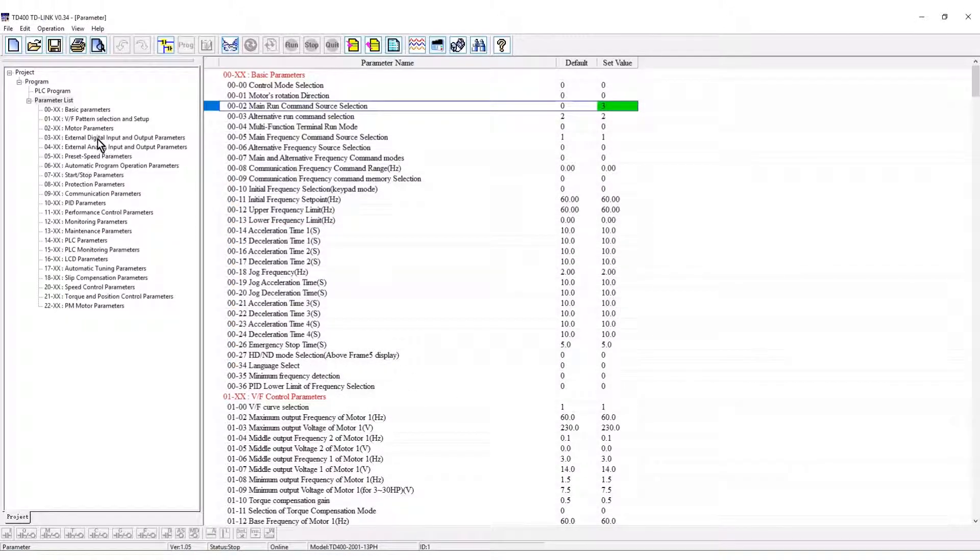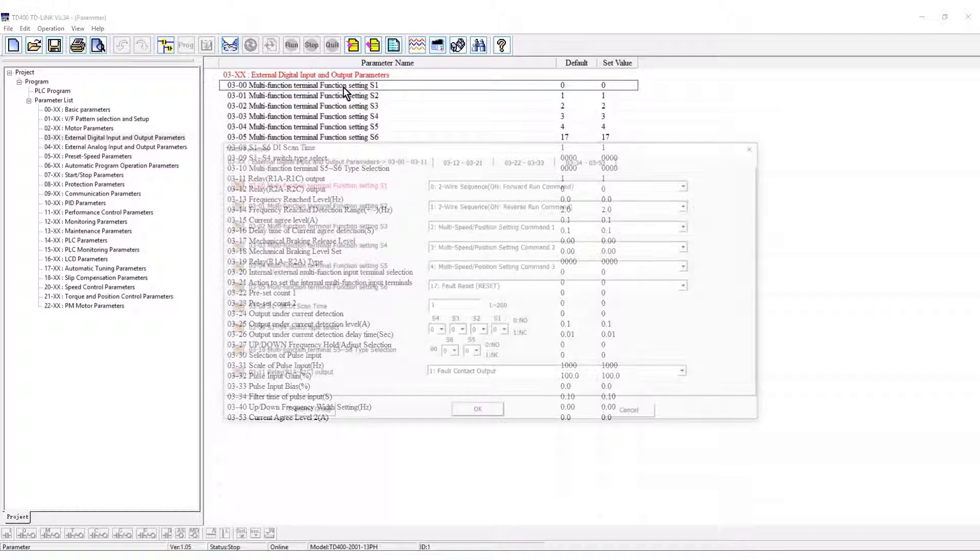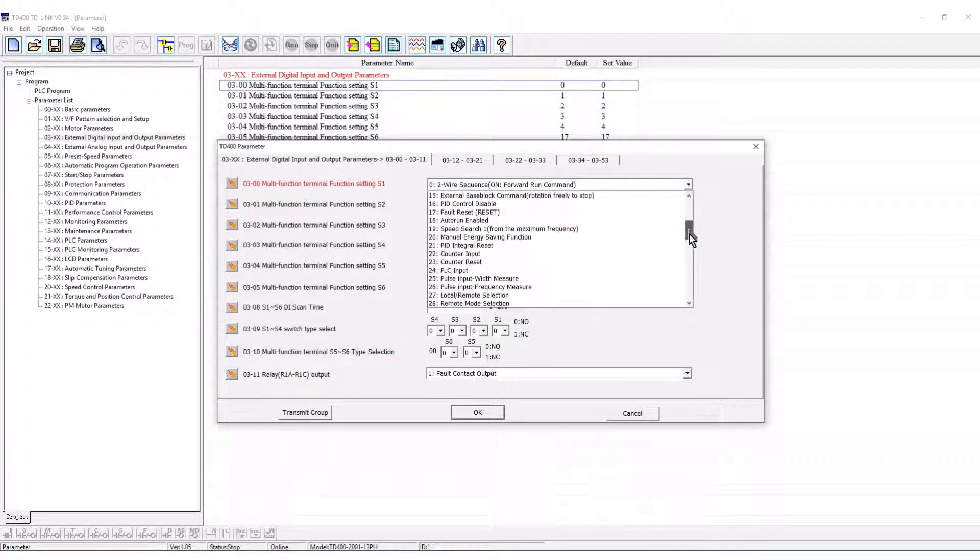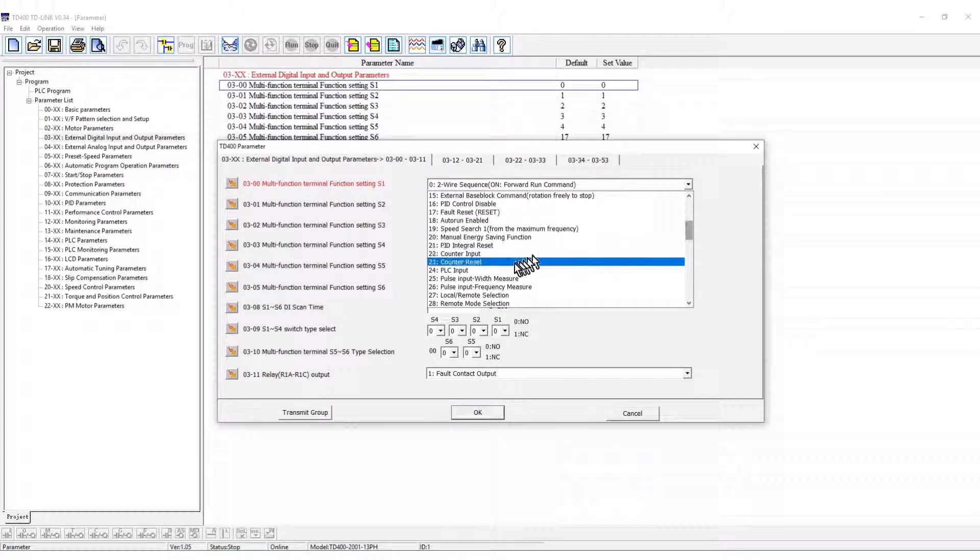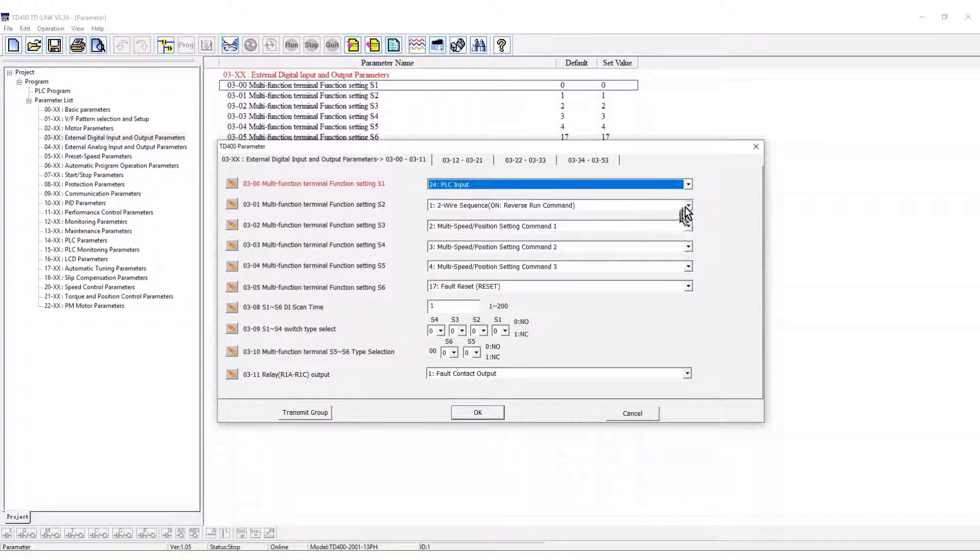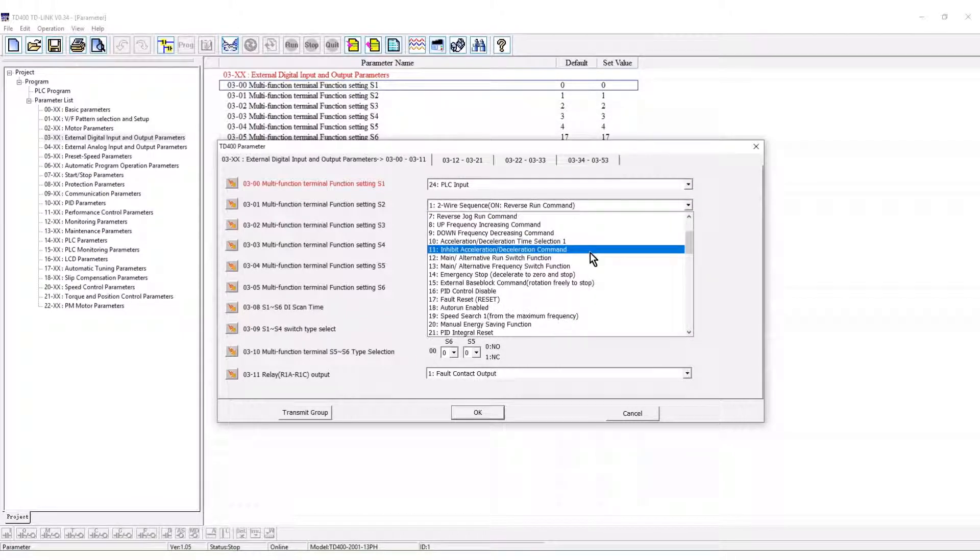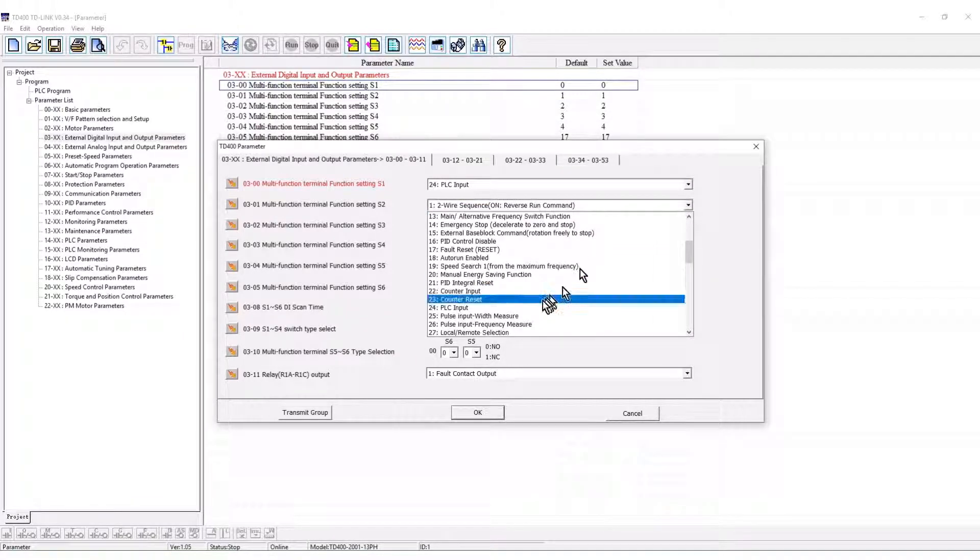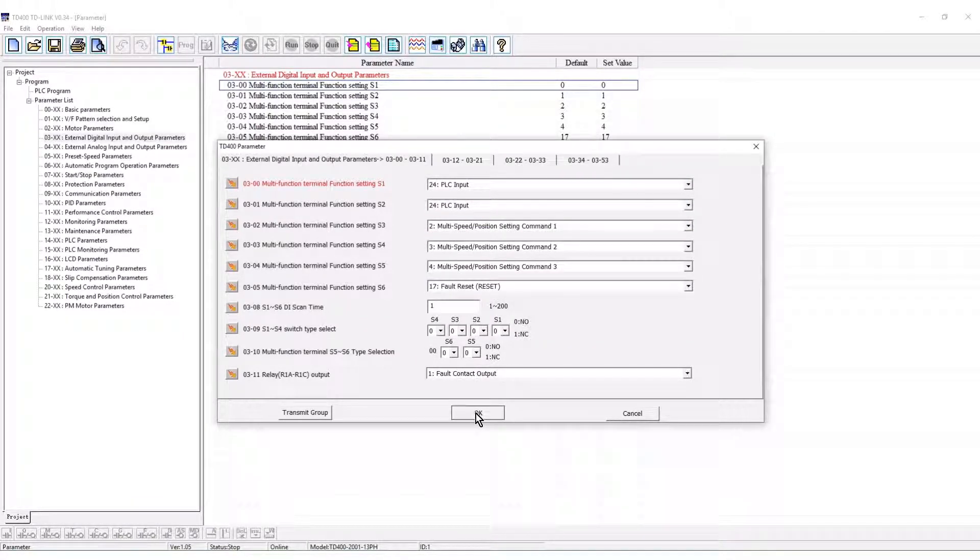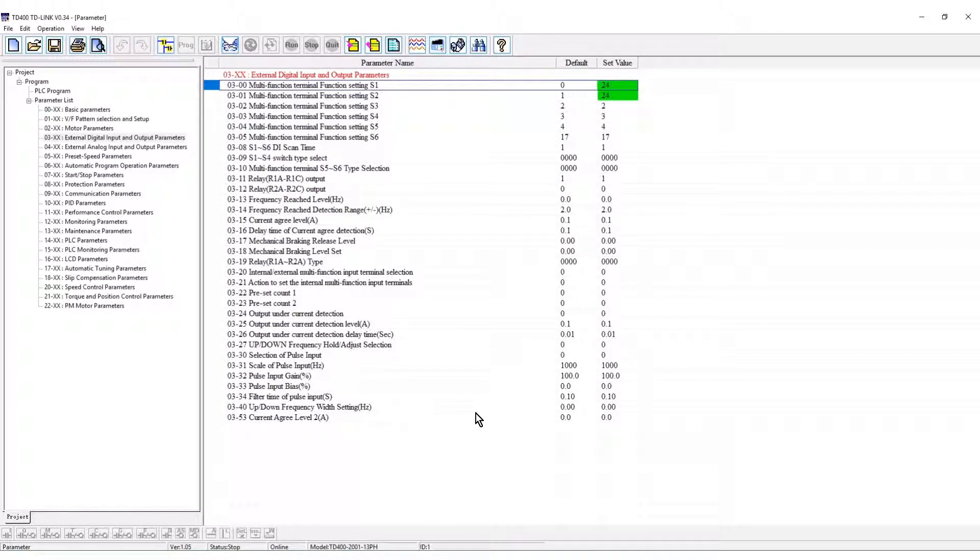Select group 3 to configure the discrete inputs. Parameter 0 is set for PLC input on S1. Parameter 1 is set for PLC input on S2. Click OK. This has set the VFD for PLC control using the discrete inputs.